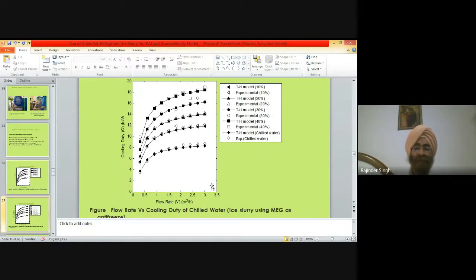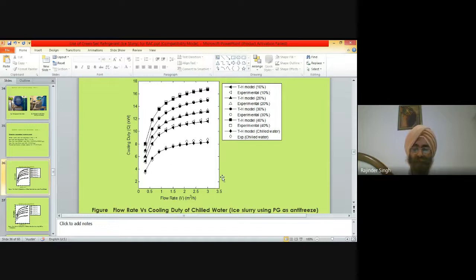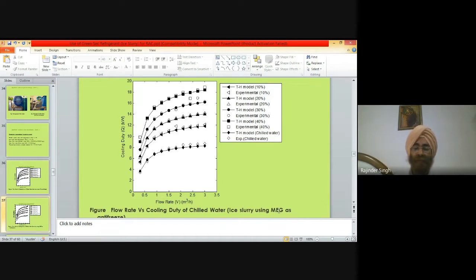The first diagram is for using propylene glycol as an antifreeze. In the second case, the glycol MEG is used, and we achieved these results. This curve is for chilled water versus normal water, and these four curves are for the ice slurry versus normal water, at 10, 20, 30, and 40%. So these are the final results I achieved in my experiments.